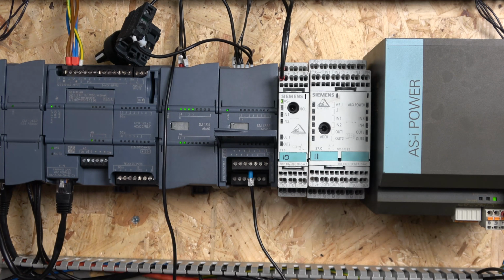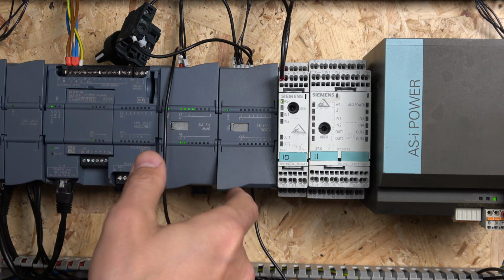Why transistor? Transistors are a lot faster than relays, and they're much more reliable. But bear in mind they come with some limitations, i.e. they come with a current limit. Do check out whichever card you're using. Make sure you understand the maximum current that can be output from your transistor card, and in our case that is 0.5 amps.